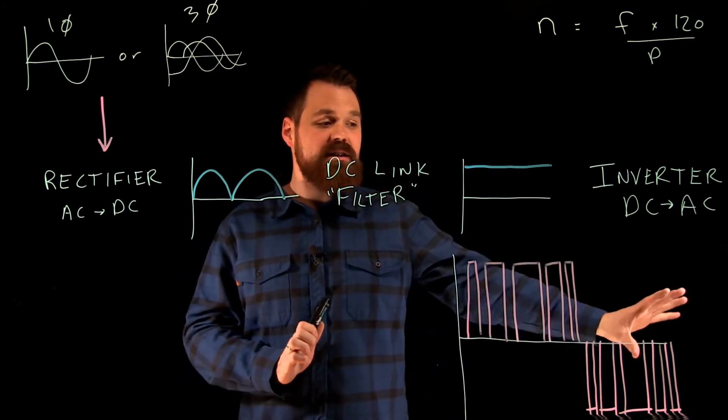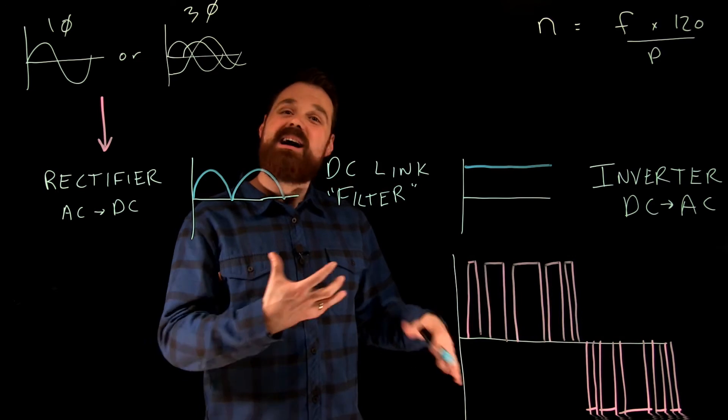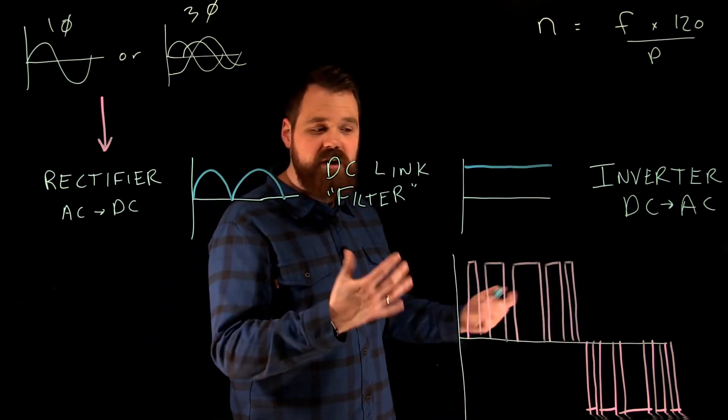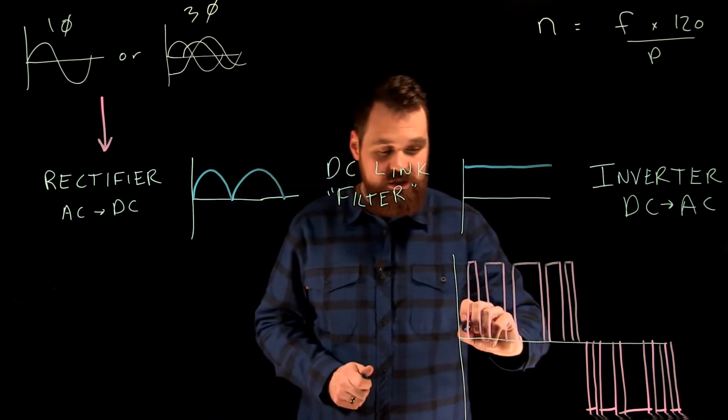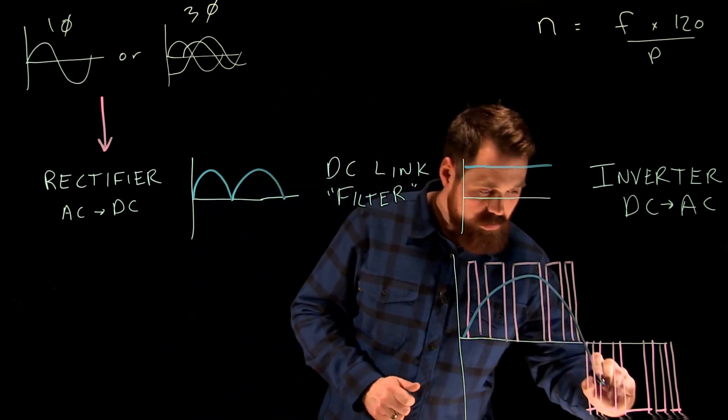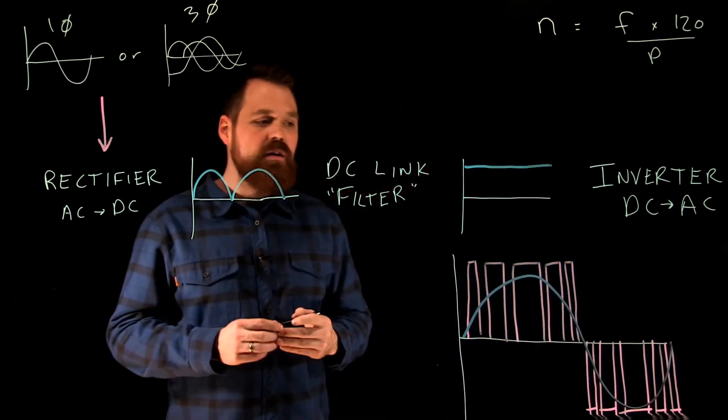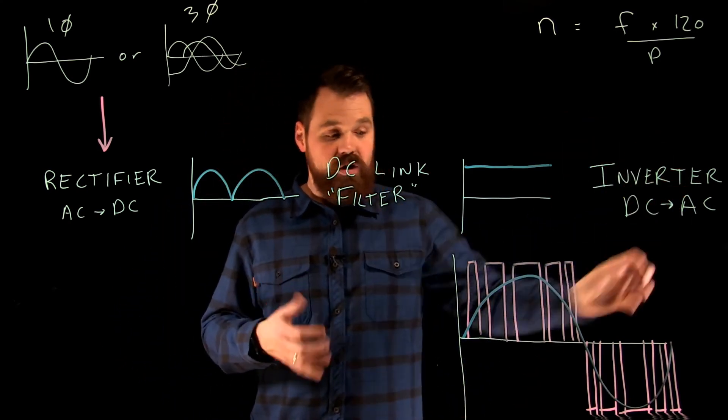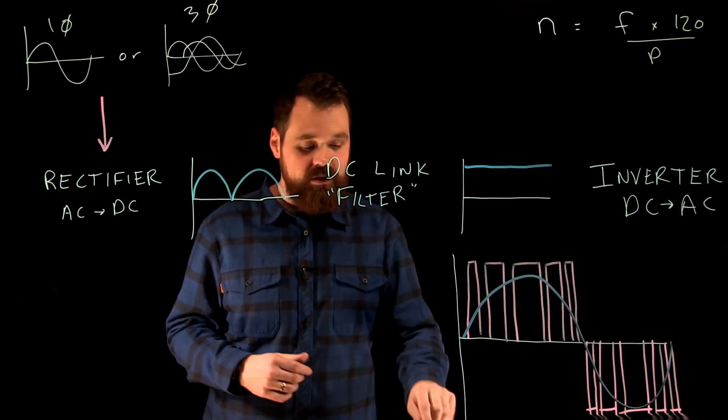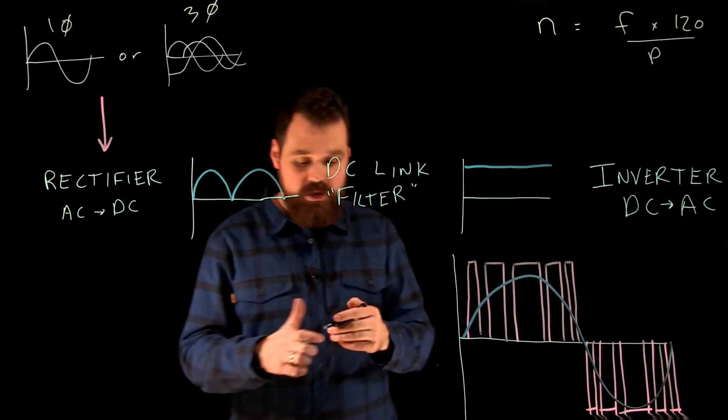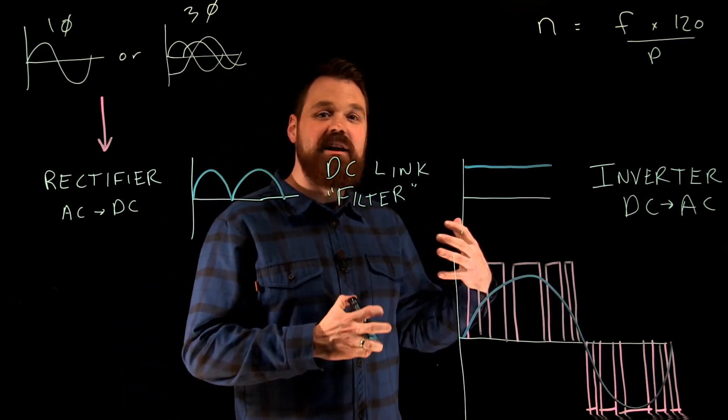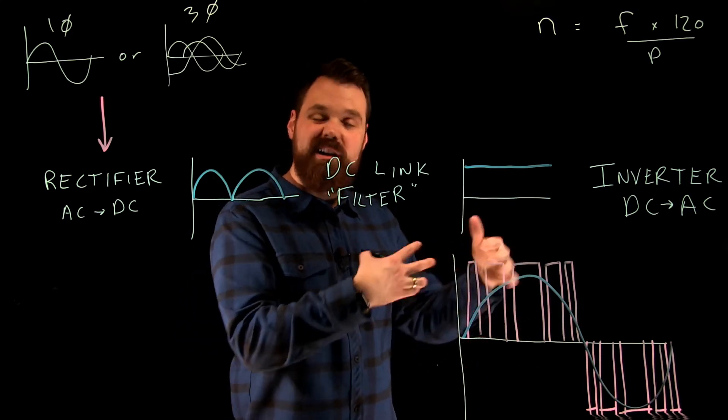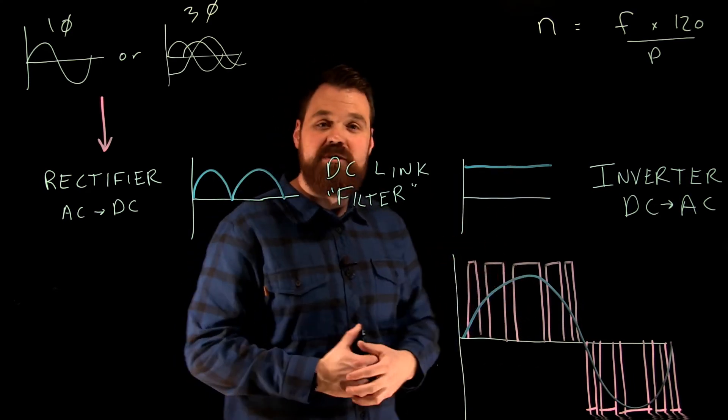Because this is happening so quick, what our load sees—the output of our VFD, which will be a three-phase motor—is it actually sees three very nice sine waves. The inverter creates three of these exactly 120 degrees apart, which gives us a really nice clean three-phase sine wave with an adjusted voltage based on the frequency that it's outputting.